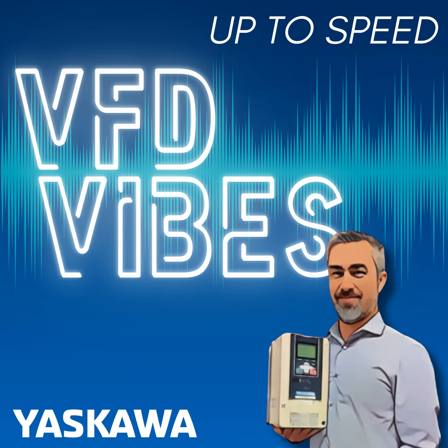Many manufacturers, including Yaskawa, offer extended warranties for installations performed by certified technicians. That's because proper installation doesn't just protect the drive, it ensures safety, reliability, and long-term ROI. A well-installed drive can operate for years without major issues, but there's more to it than wiring. The next two pieces of the puzzle are the motor and the motor cable. Let's talk about the motor first.